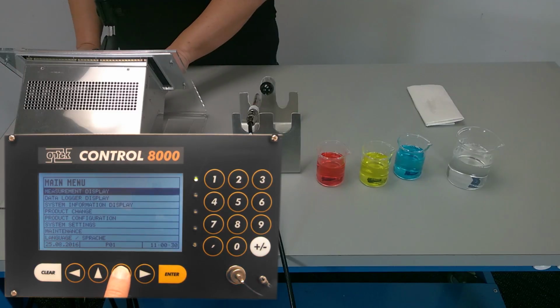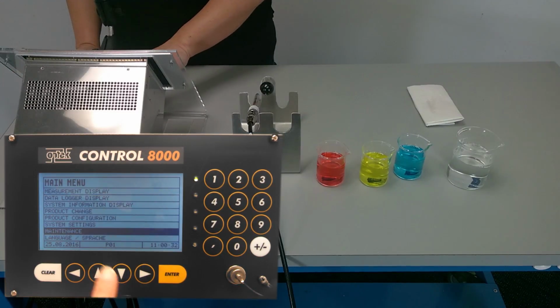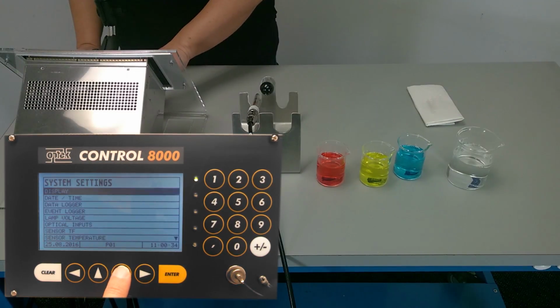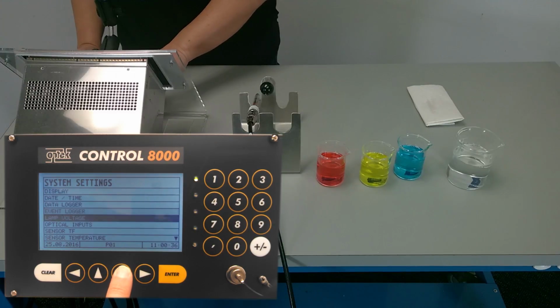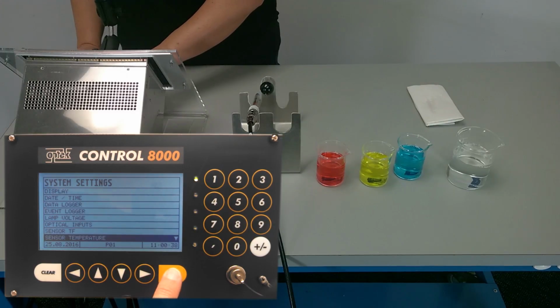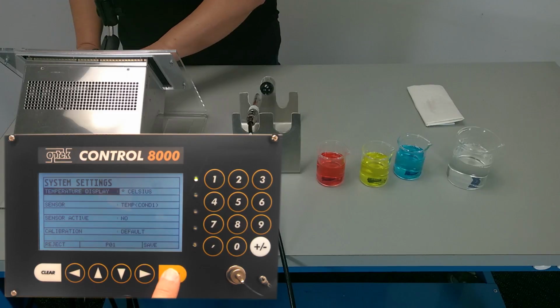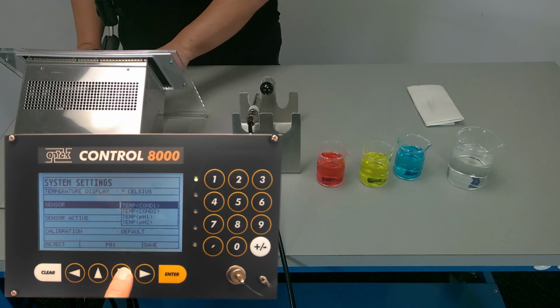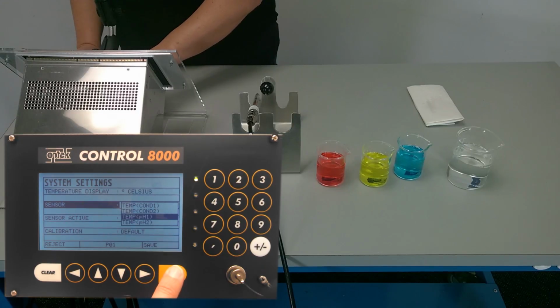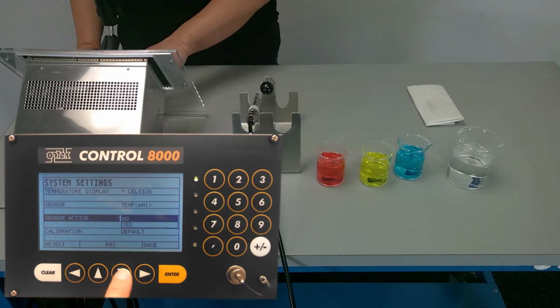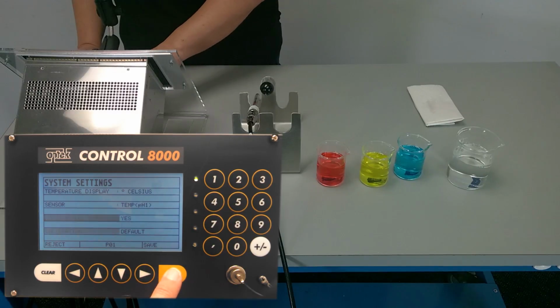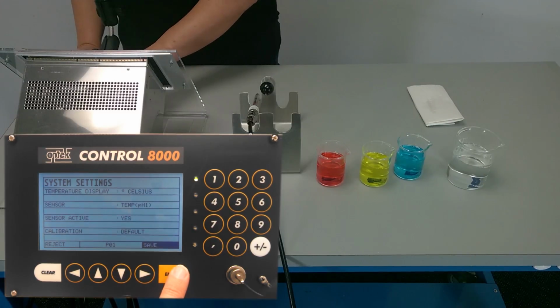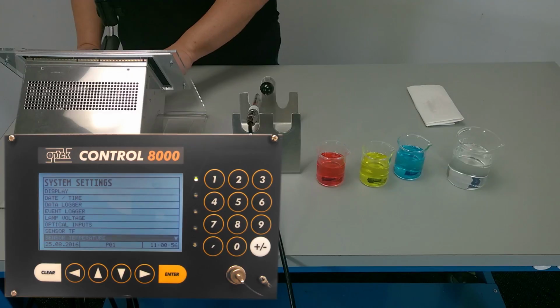So what you first will do is scroll down to System Settings and hit Enter. From here, you're going to scroll to Sensor Temperature and hit Enter. The converter will read in either degrees Celsius or degrees Fahrenheit. For the sensor, we are going to select Temp pH1, and we are going to hit Enter and select Yes for Sensor Active. Scroll to Save and hit Enter.